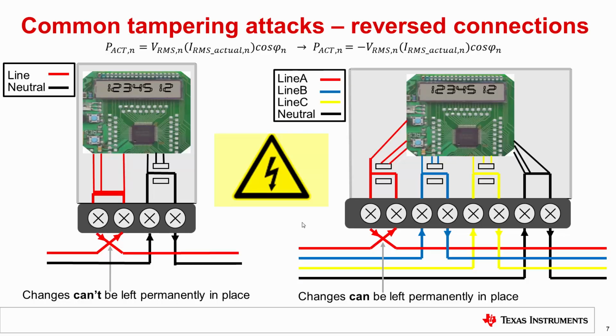Once this value is accumulated, it subtracts from the total accumulated energy consumption readings, thereby reducing what customers will be charged. For the one-phase scenario, care has to be taken, though, to make sure that the reverse connections have not been left in place long enough for the total accumulated energy consumption readings to read a negative value, which would be a red flag for utilities if a customer consumes and does not produce any electricity.